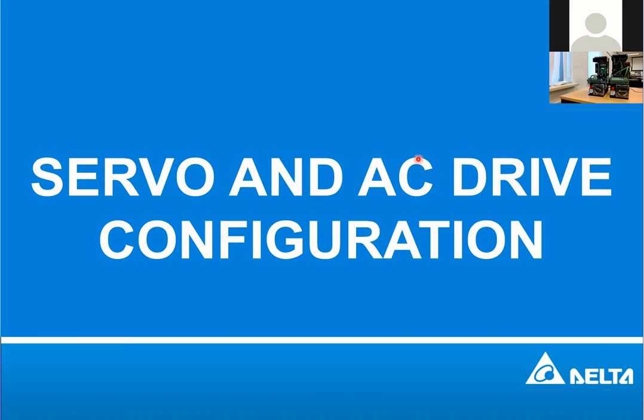Then the CANopen network is extended to a CANopen communication card inserted in an MS300, which is an inverter. On the MS300, you can see a tiny cable on the digital input MI3. There we enable a function called quick stop. We could use that function to quickly disable the inverter in case of emergency. This MI3 is connected and shorted, so the function is enabled. If it's opened, the inverter should stop for emergency purposes.